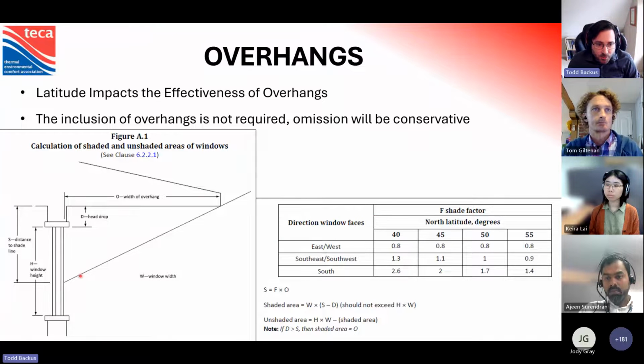Overhangs, you can provide overhangs. You do not have to. The standard says specifically you do not have to include overhangs, but what it does is it helps provide shading, so it decreases your cooling requirements. So it's up to you. If you omit them, your calculation will be more conservative.